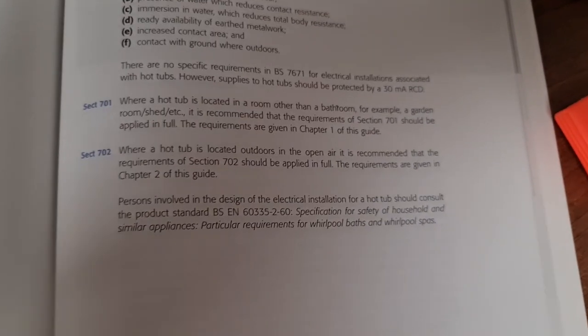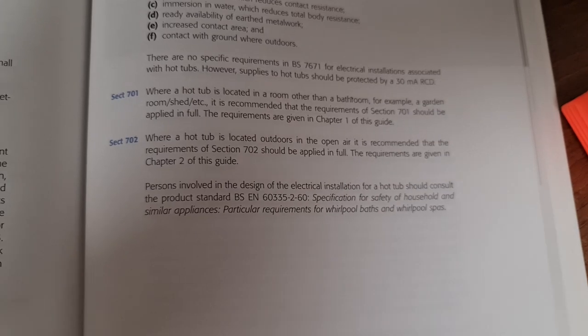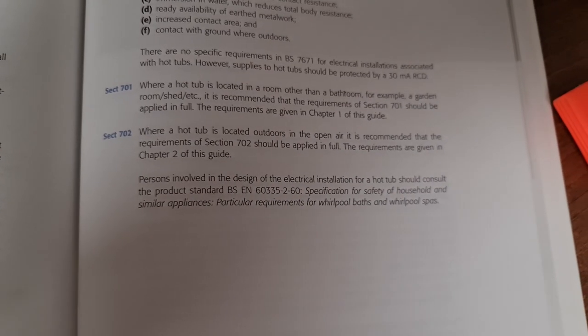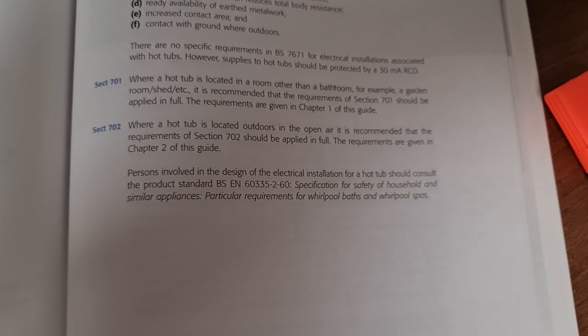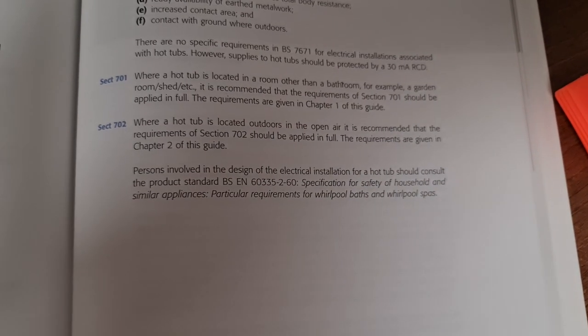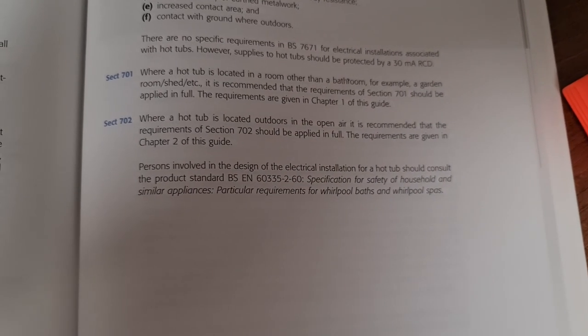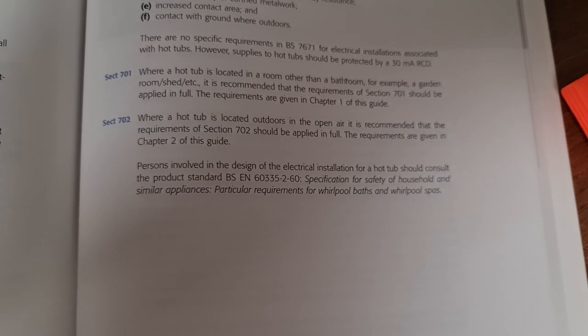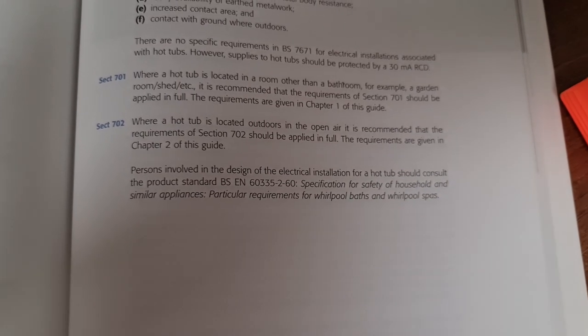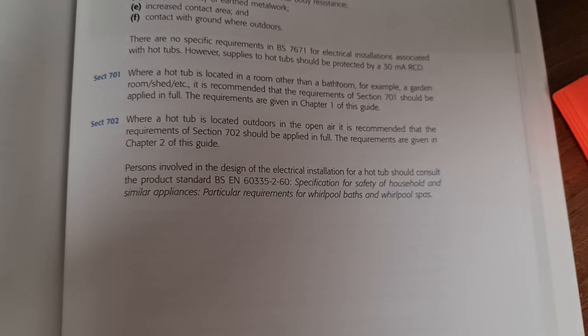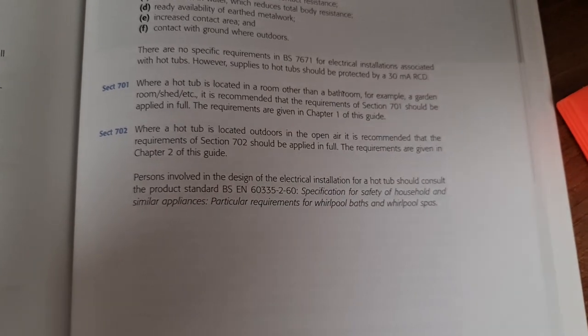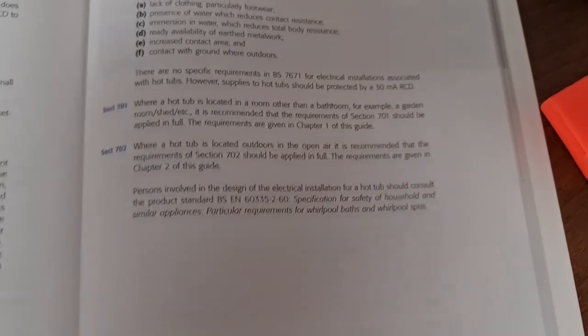It then goes on to talk about hot tubs being used in rooms and outside, and we'll look specifically at the outdoors one because that's what we've dealt with on this install. Section 702 says where a hot tub is located outdoors in the open air, it is recommended that the requirements of section 702 should be applied in full, and the requirements are given in chapter 2 of this guide.